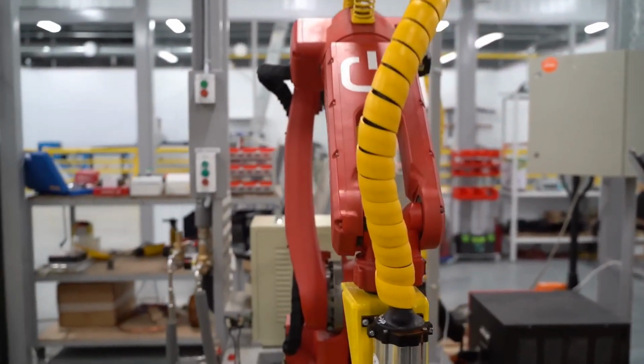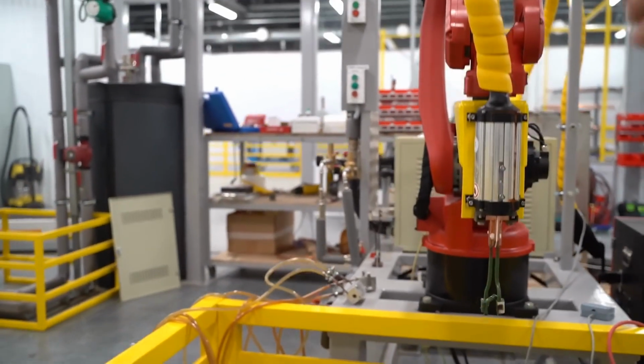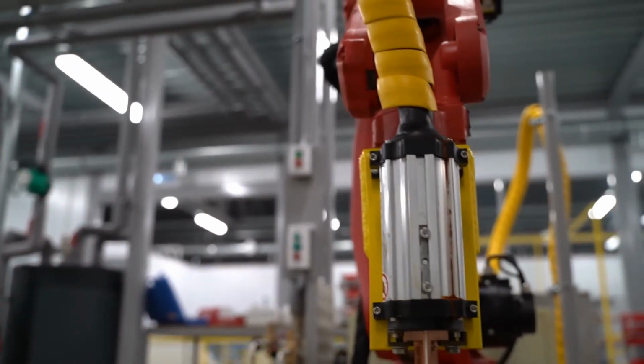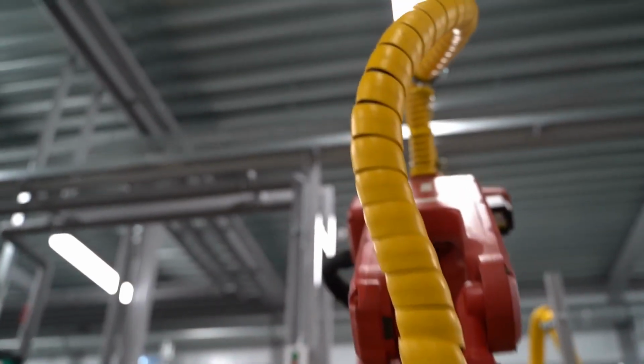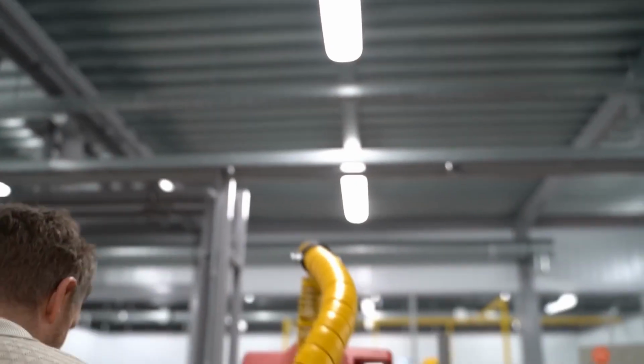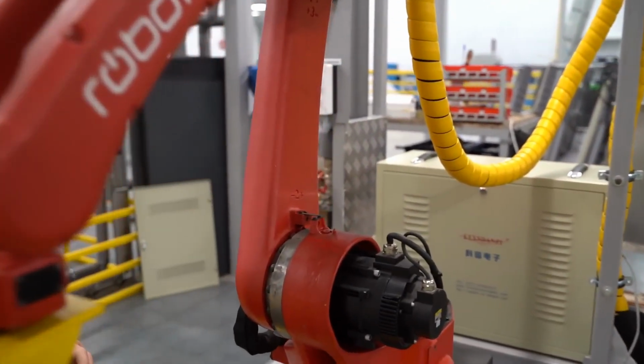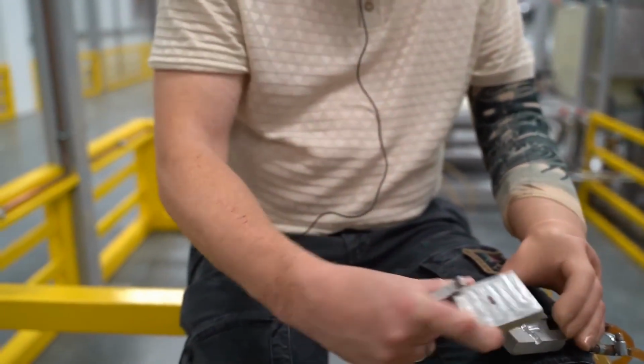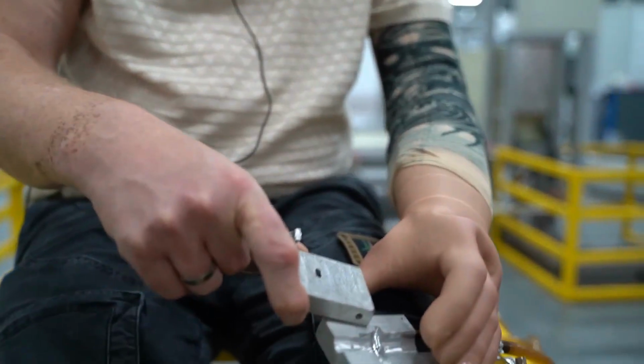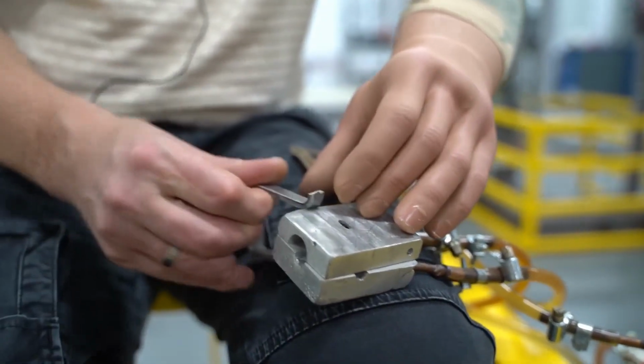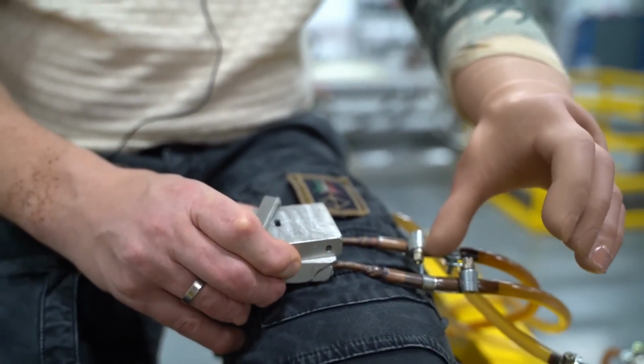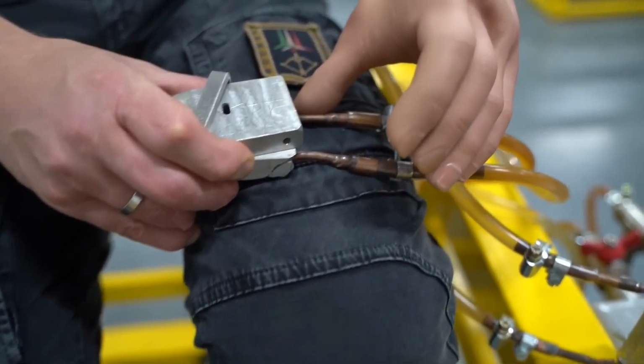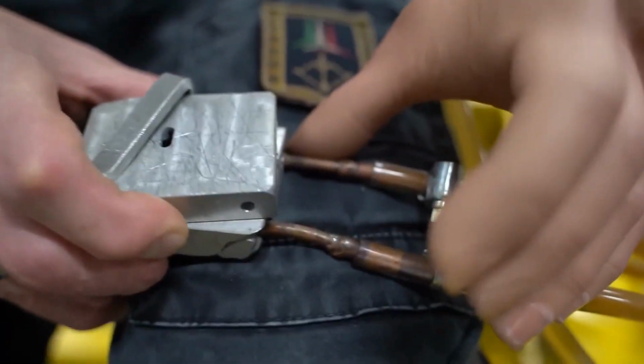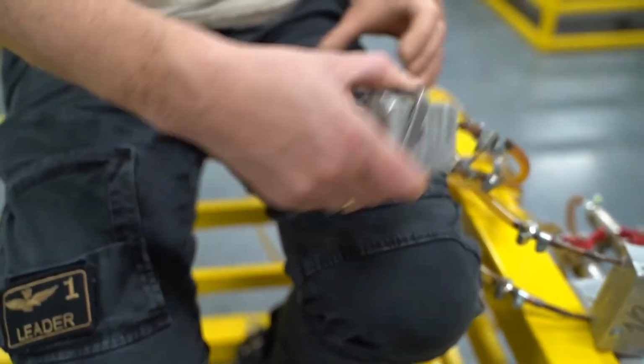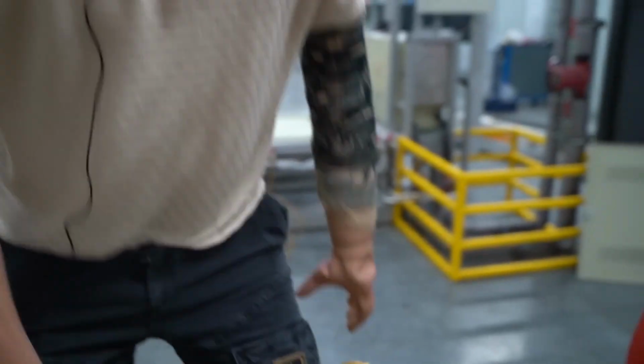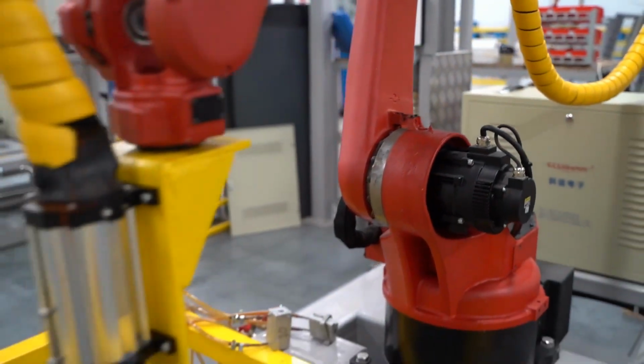When soldering particularly sensitive elements like sight glasses and EEVs, many people typically wrap them with rags. But we believe that's not a technological solution, so we made this device instead. We took it and cast it. It positions the housing for soldering. We cast an aluminum fixture for the EEV. It goes here, closed with this clamp, and water is pumped through. The temperature inside during soldering stays below 55 degrees, which suits us. We made the sight glasses the same way. This one is for the EEV. There you go.